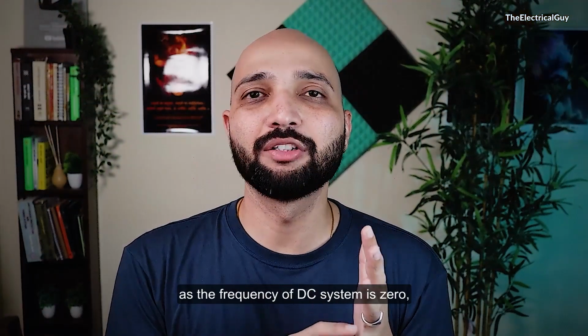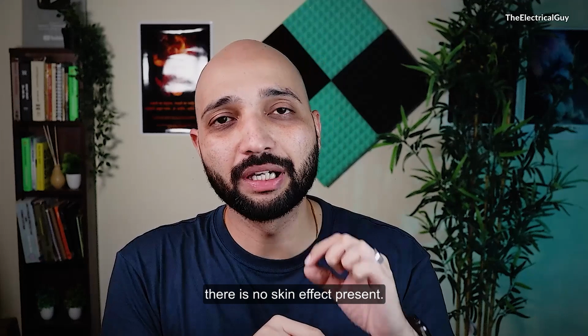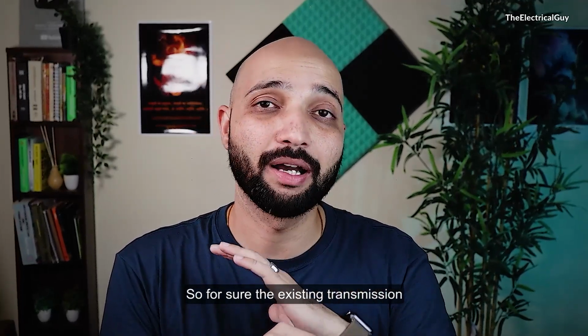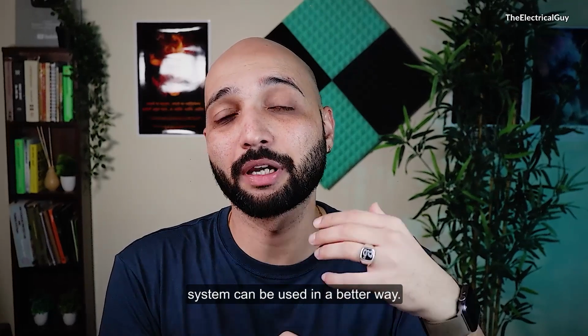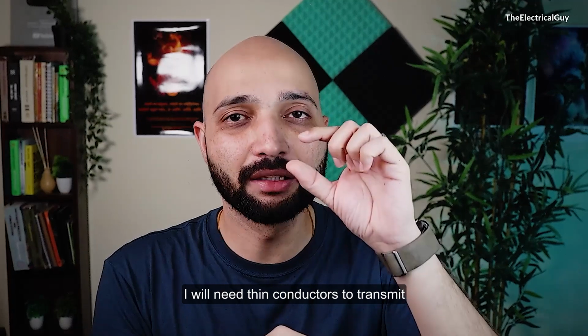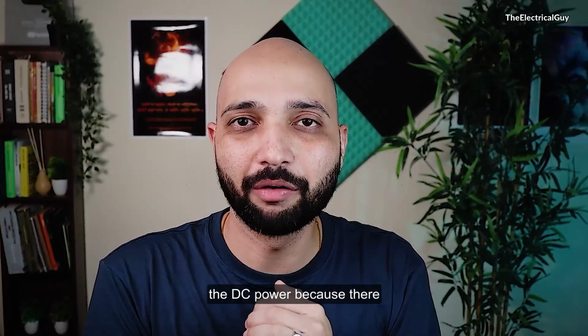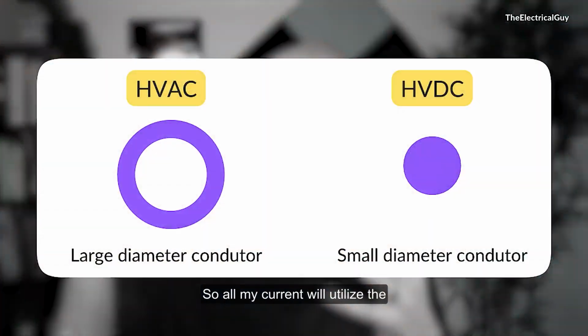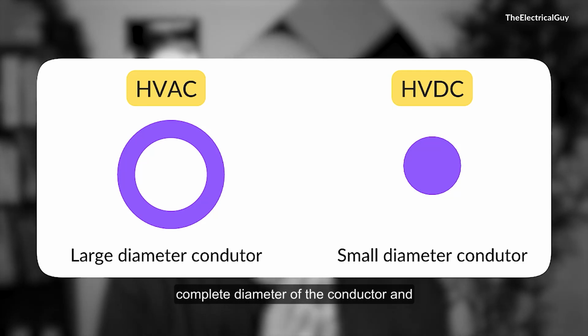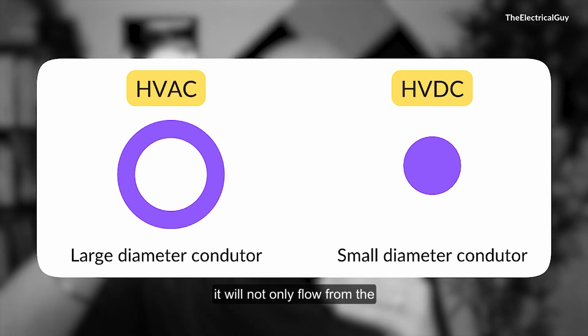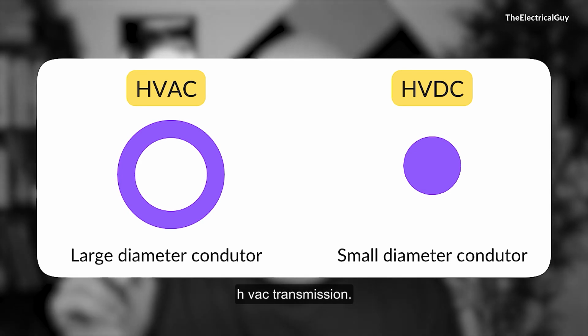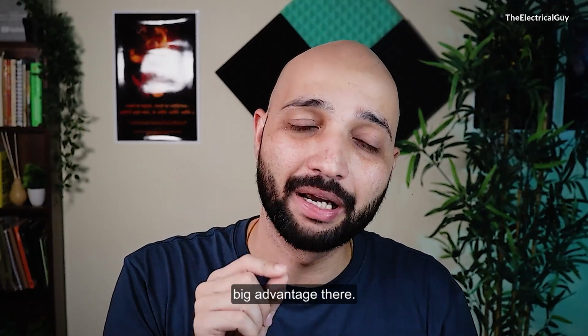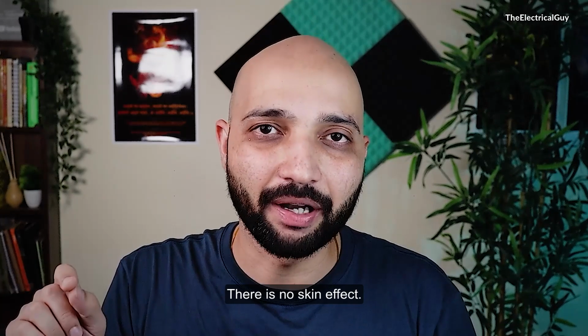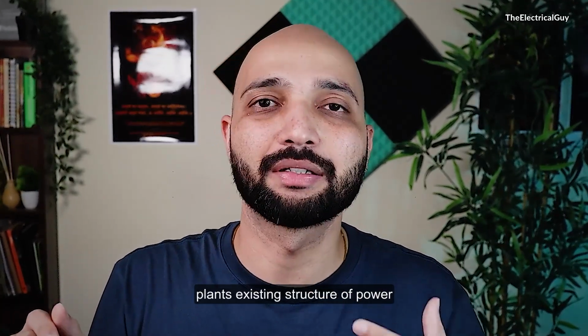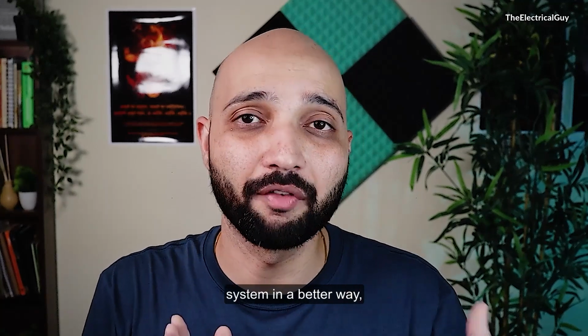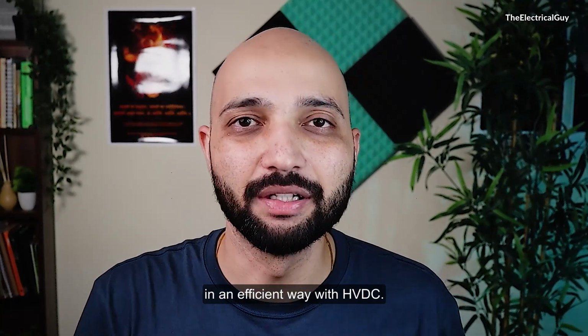In a DC system, as the frequency of DC is zero, there is no skin effect present, so the existing transmission system can be used in a better way. I will need thinner conductors to transmit DC power because there is no skin effect, so all the current will utilize the complete diameter of the conductor, and it will not only flow from the surface of the conductor, which is the problem with HVAC transmission. So this is again one of the big advantages, there is no skin effect, and I'm utilizing my existing power plants and existing power system structure in a better, more efficient way with HVDC.